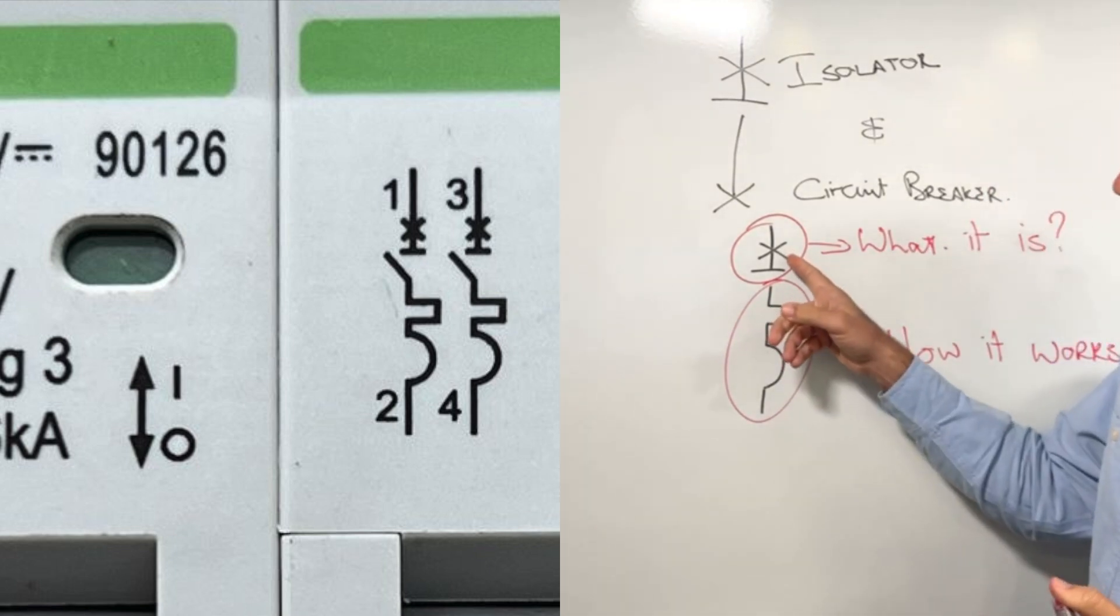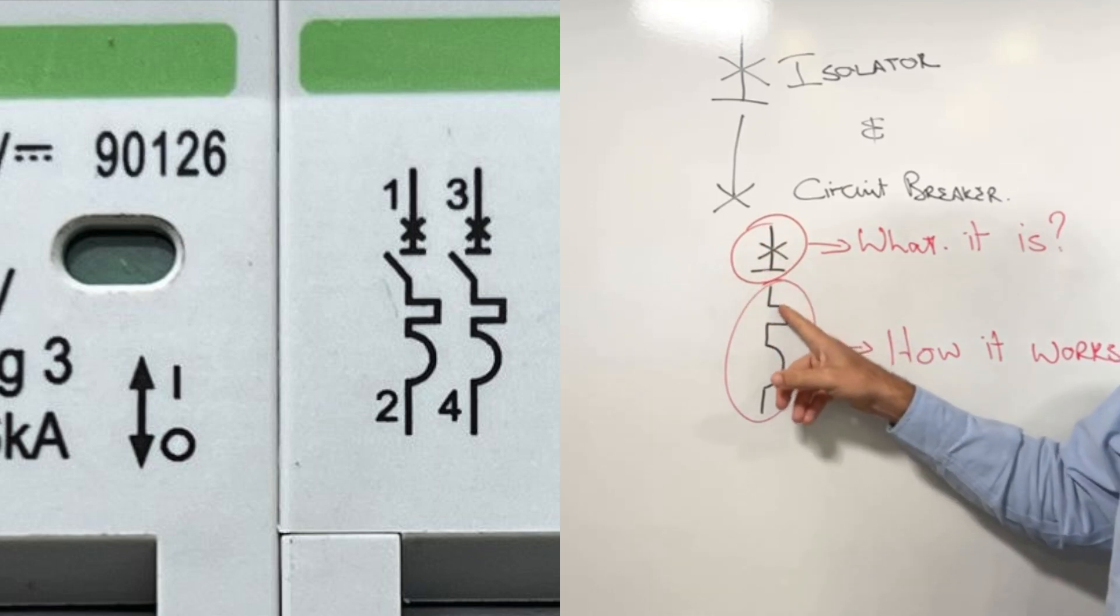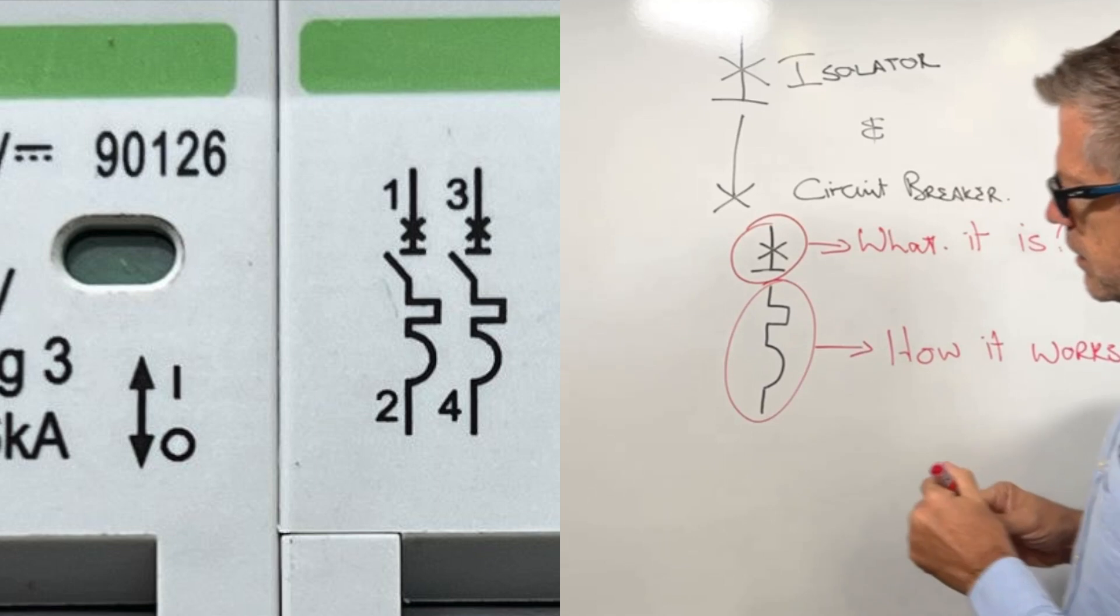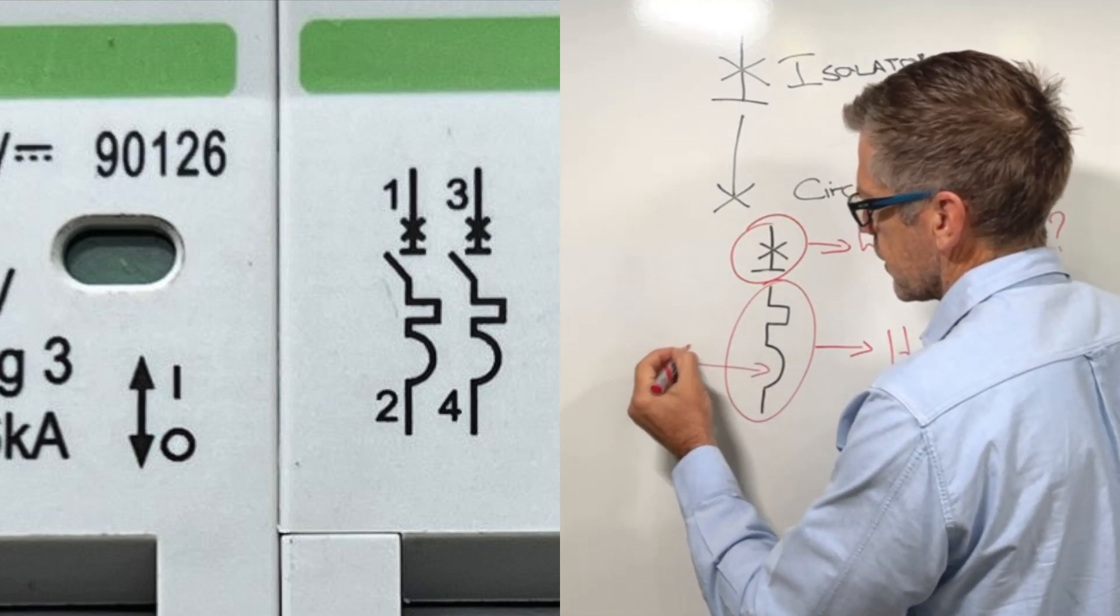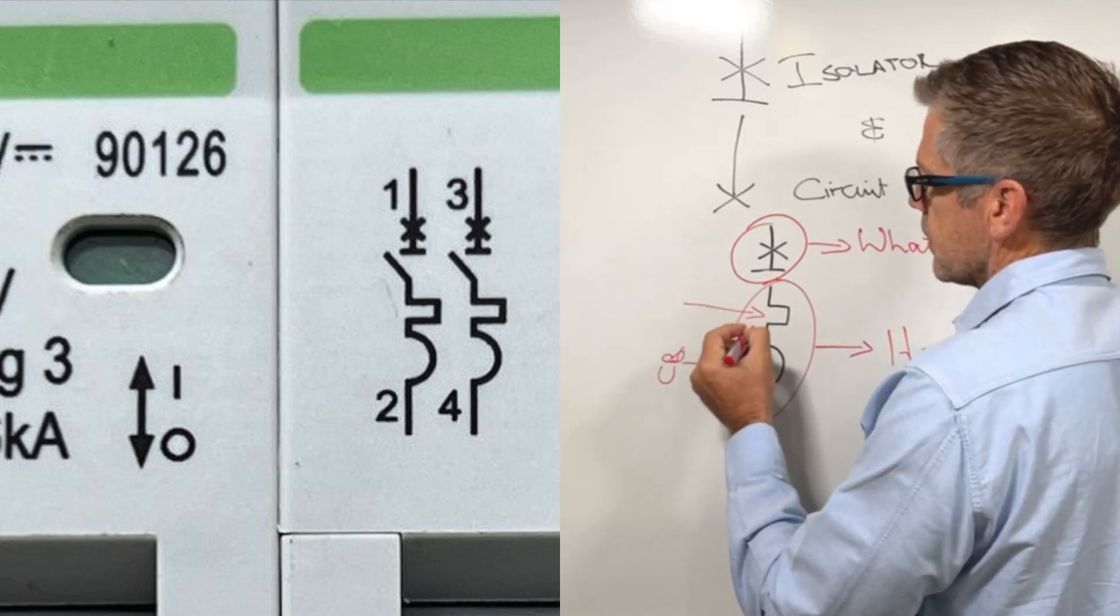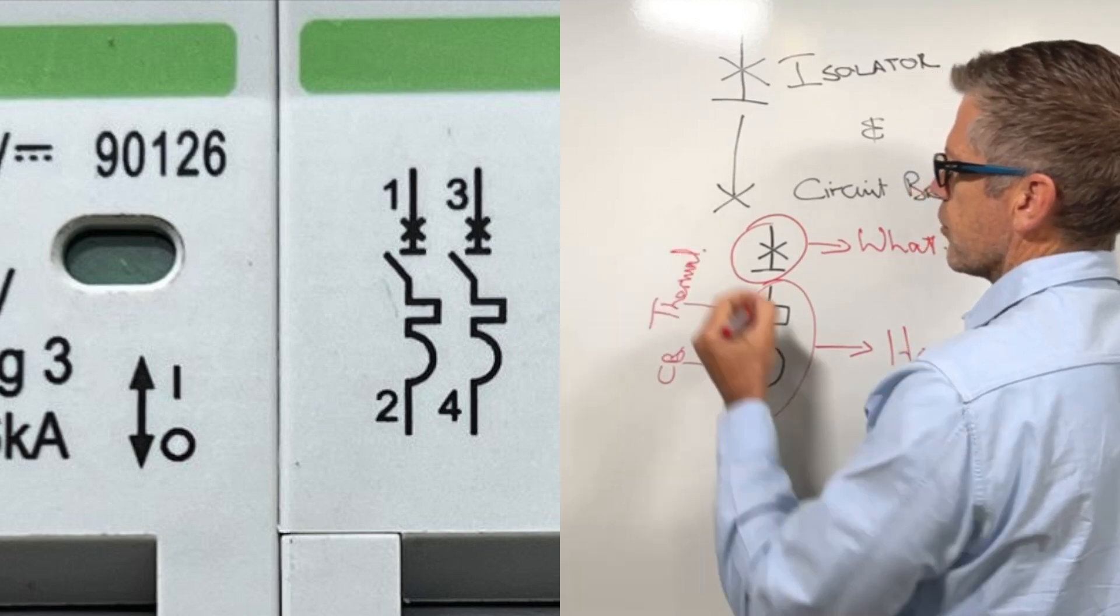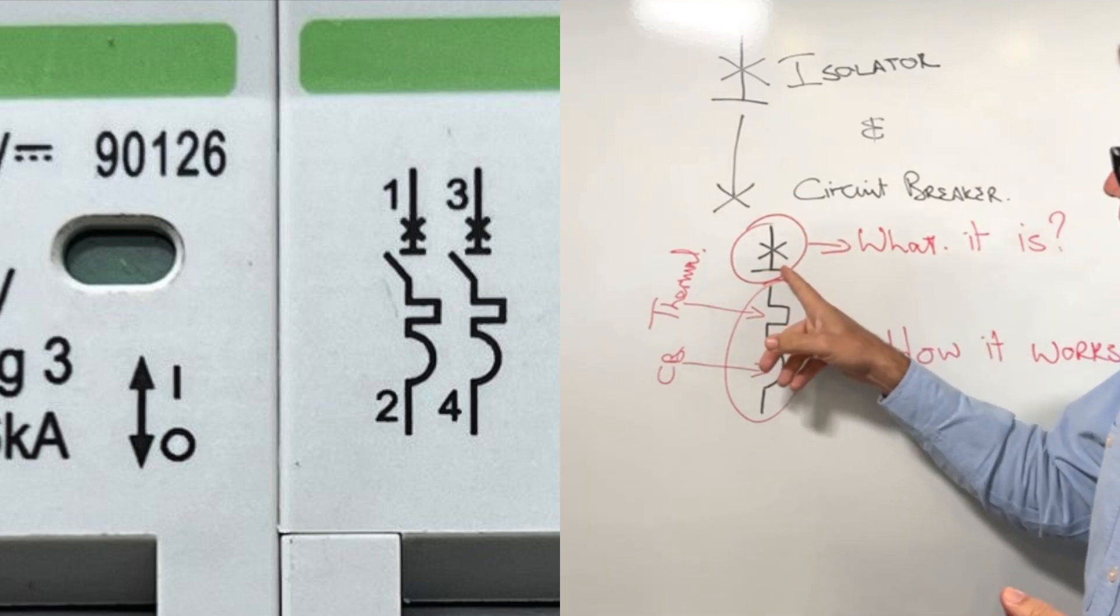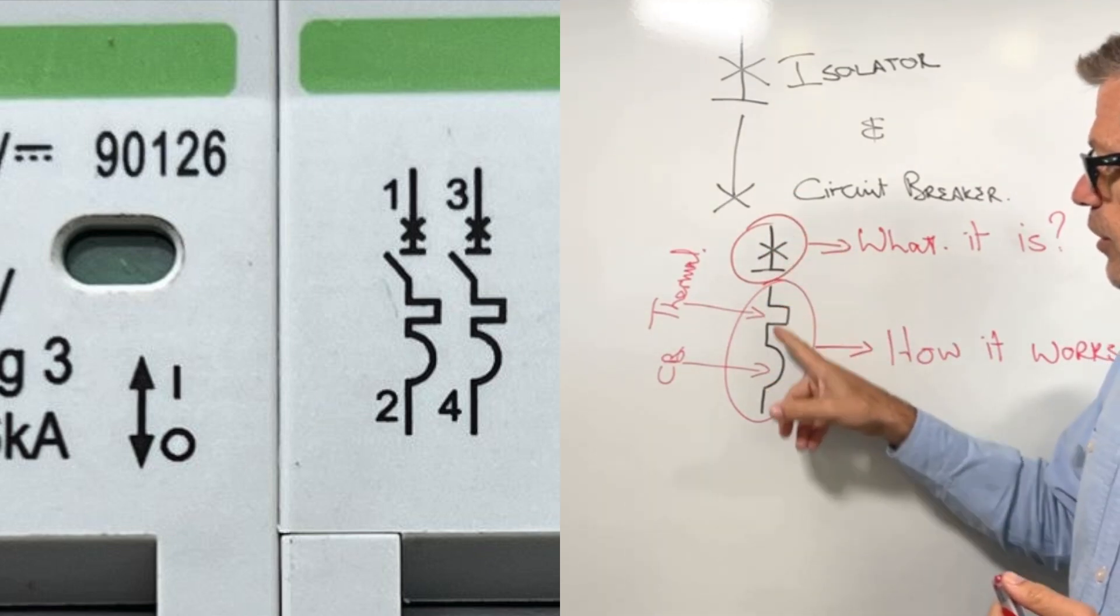The top section tells you that this is both a circuit breaker and an isolator, and the bottom section tells you what it does. This is the IEC symbol for circuit breaker, which means that it will trip on overload. And that is a symbol that looks at thermal protection. So this is a circuit breaker and an isolator with thermal and overload function.